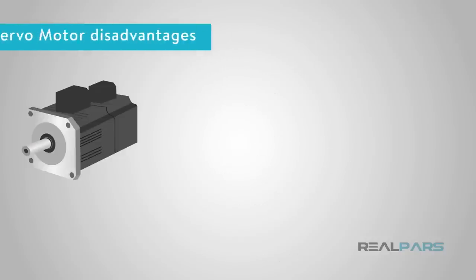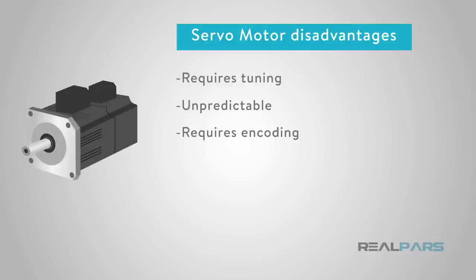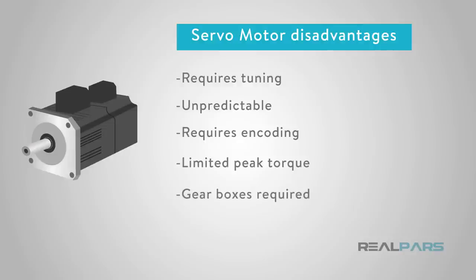The top servo motor disadvantages are: servo motors require tuning to stabilize the feedback loop; servo motors will become unpredictable when something breaks, so safety circuits are required; complex controller requires encoder and electronic support; peak torque is limited to a 1% duty cycle and servo motors can be damaged by sustained overload; gearboxes are often required to deliver power at higher speeds; and higher overall cost — the installation cost of a servo motor system may be higher than that of a stepper motor due to the requirement for feedback components.